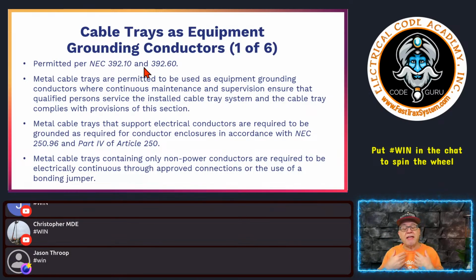Okay, today we're talking about using that support system as an equipment grounding conductor. Does the code allow this? As you can see right here, first of all, cable trays are permitted. 392.10 gives you the list of permitted uses. Remember that, and then of course you've got 392.12, which is the uses not permitted, or what you can't do with a cable tray.